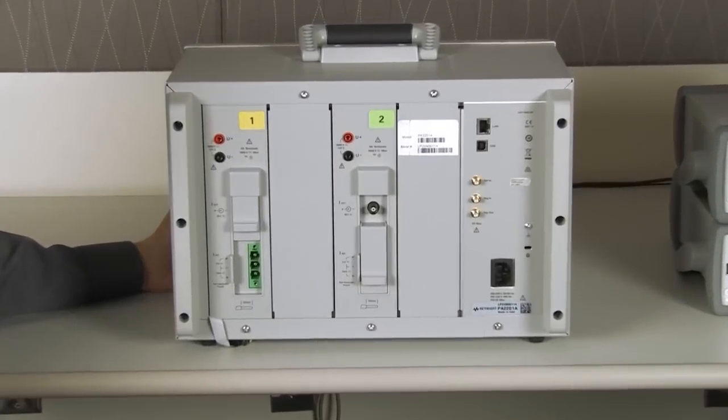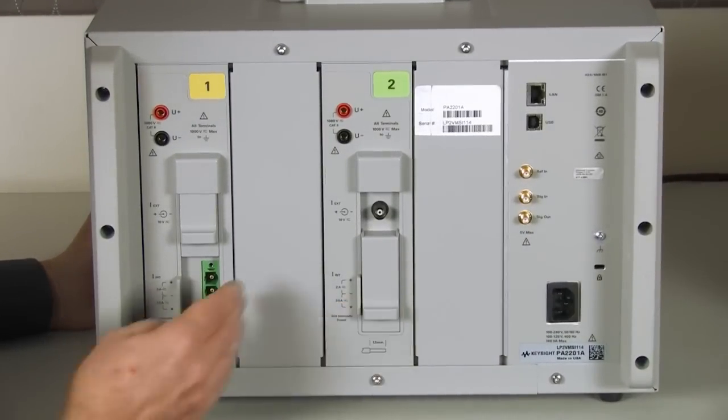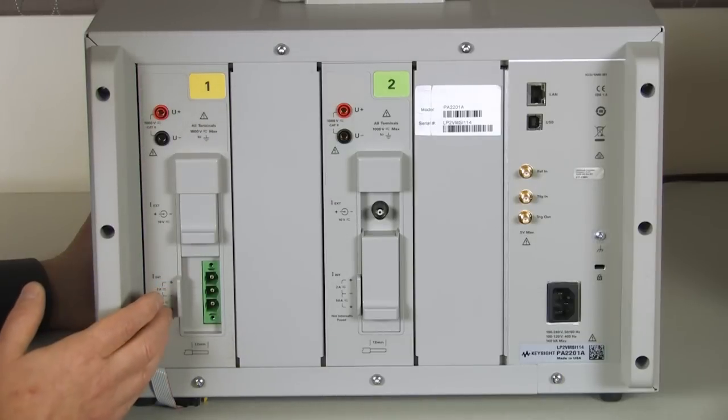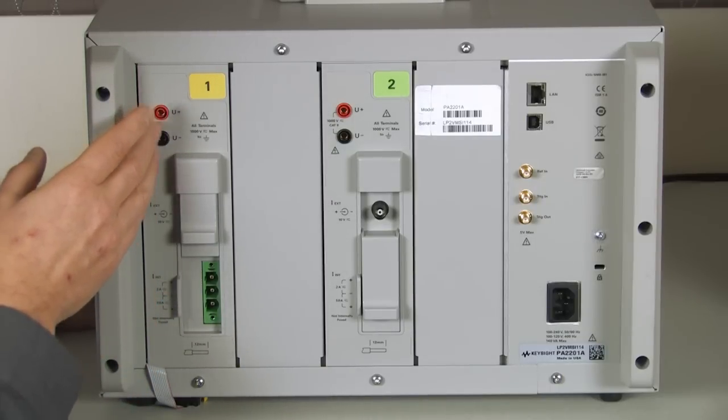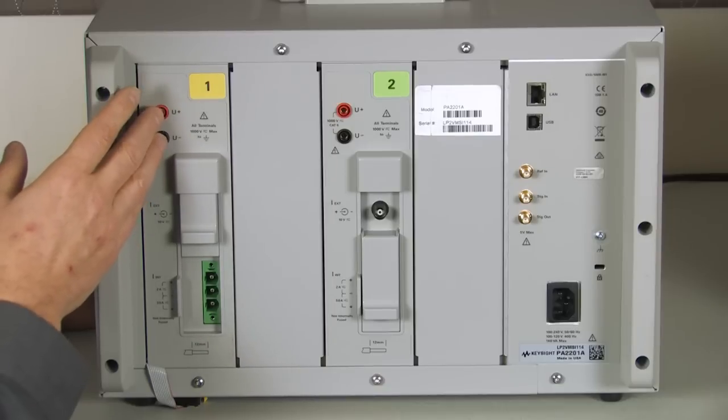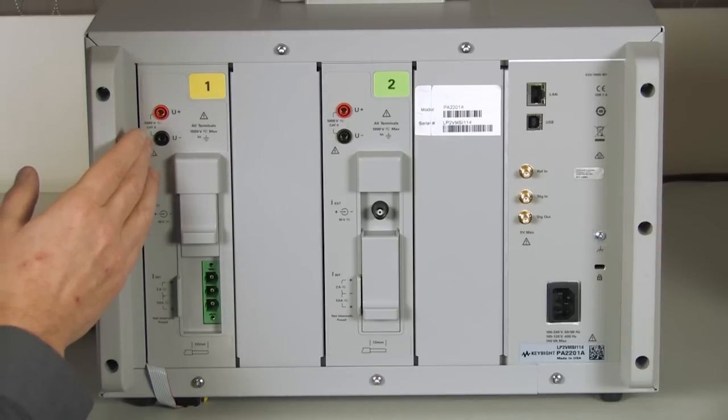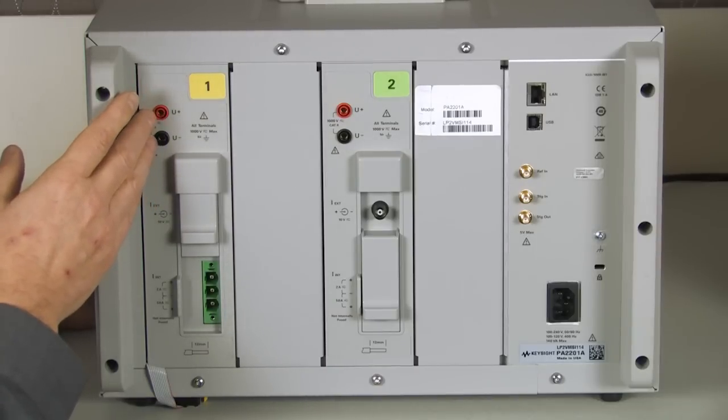First thing we're going to do is give you a tour of the connections on the back of the instrument. As we look at the rear of the instrument, the first thing you'll notice are the two power channels. Unlike an oscilloscope, a power analyzer power channel has both voltage and current connections. For the voltage connections, we use banana plug connectors, and these connectors are up to 1,000 volts RMS.